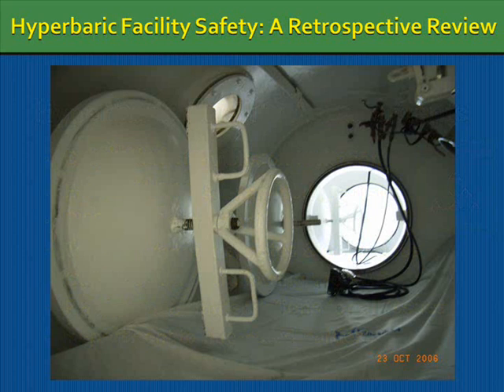Okay, just to give you a couple of visual pictures here, what you might see out there in terms of remote facilities. So we have a chamber. That's very, very typical of a deck decompression chamber that's been made a bit more comfortable for injured people to be treated on, and the patient's going to be in there for between 90 minutes if they're lucky to 4.5 hours. But have a look at where the door sits and where the mattress is. So you can imagine when you have an accident or some incident and you do get inside the chamber and the patient's already lying down blocking the doorway. Many of the people have no concept of the risks they're facing until you can explain to them how are you going to get the door open in an emergency when the patient is no longer cooperating with you.